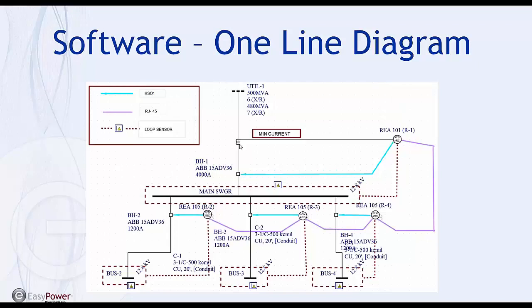So you can see you have a CT for the main unit. It just requires a minimum amount of current so you don't have spurious trips, and that information is received by the main unit. You have an RJ45 cable that is daisy chained to all the extension units, and that's how the current information is passed to the extension units. They have to get their current information from the main, but they have dedicated sensors that are protecting each bus.